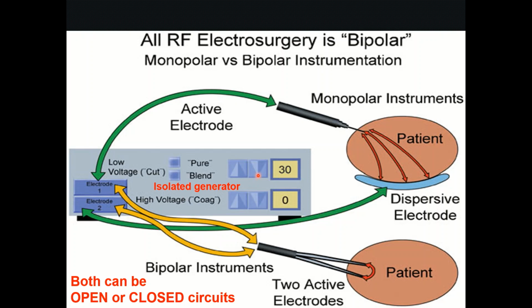Now this is the typical electrosurgical unit. Here what is happening? This is the dispersive plate, right? So the current comes to the patient, and from the patient through a dispersive electrode it comes back inside, right? That means this is an isolated generator. Isolated why? Because it is generating the current and bringing the current back, right? Now what happens in a bipolar? This is basically a unipolar, or monopolar. Why? Because the current is not being brought back by the same electrode. There is only one pole in the electrode, so it is monopolar, right?